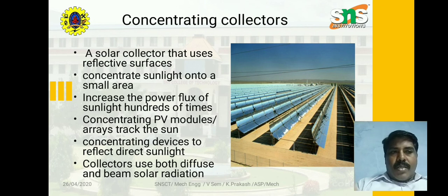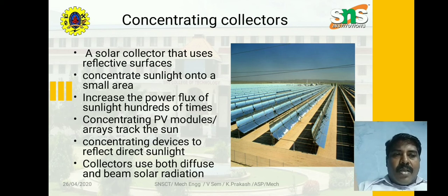This is the use of a concentrating collector, where most of the solar radiation is absorbed and can be trapped to heat the water. Here the collector area becomes smaller, as the solar radiation absorbed is pointed towards the particular receiver area. The efficiency increase allows the water to be used for industrial purposes, with temperatures of more than 200 to 250 degrees Celsius.